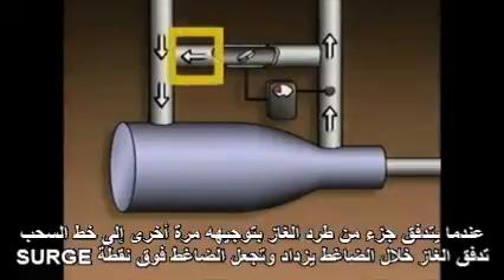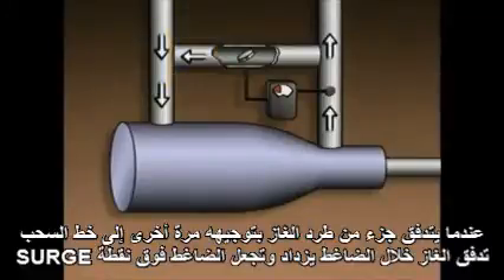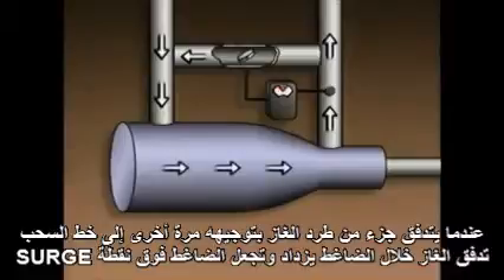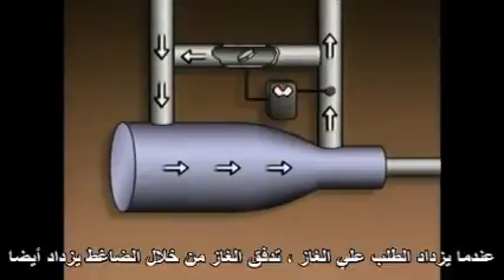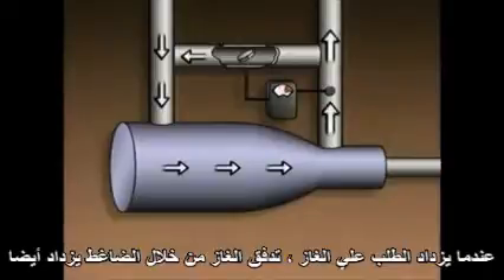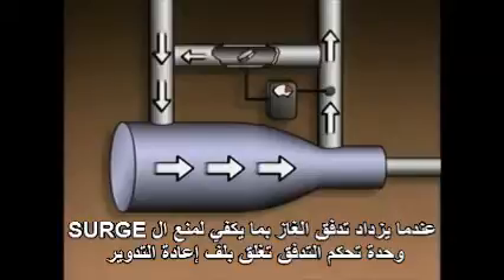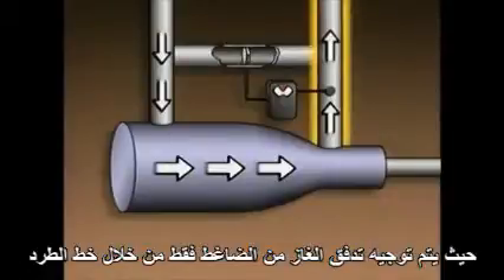When a portion of the discharge gas flow is routed back into the suction piping, the gas flow through the compressor increases and it stays above the surge point. When demand increases, gas flow through the compressor also increases. When the gas flow is high enough to prevent surge, the flow controller closes the recirculation valve. The gas flow from the compressor is then directed only through the discharge pipe.